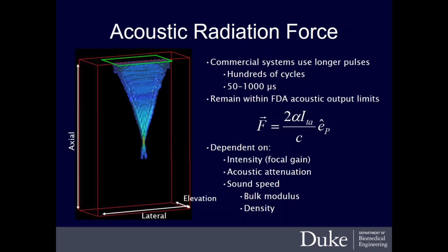Jumping over more specifically to what the ultrasonic shear wave speed systems do: to generate that deformation that a clinician would potentially do with their hand through manual palpation, we instead utilize acoustic radiation force. An acoustic radiation force is generated in the same exact acoustic footprint that a focused B-mode or Doppler pulse would go in, but typically we use slightly longer pulses to generate measurable displacements in the tissue.